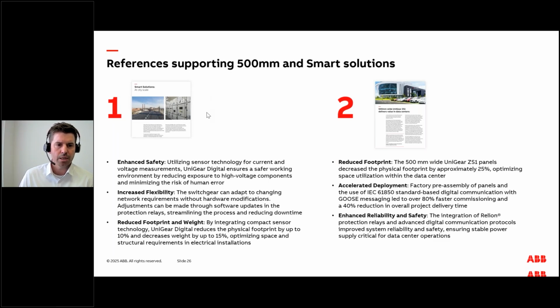The first reference is a project related to smart solutions, or the medium voltage switchgear, where sensors, so-called low power instrument transformers, are used. This installation is actually done in Finland, and here the substation helps the customer tackle the challenges of today's electrical network, like improving the safety level of the installation, where sensors are an ideal component in increasing the safety level for operators.